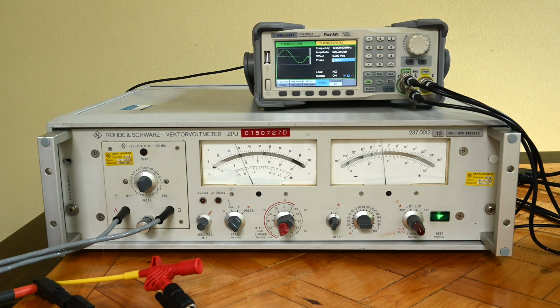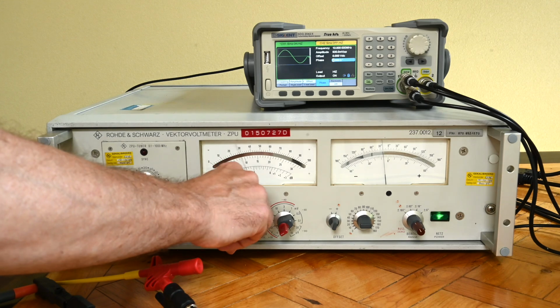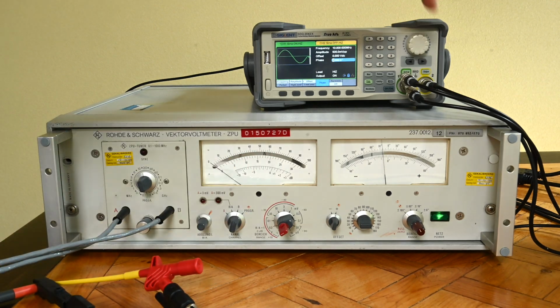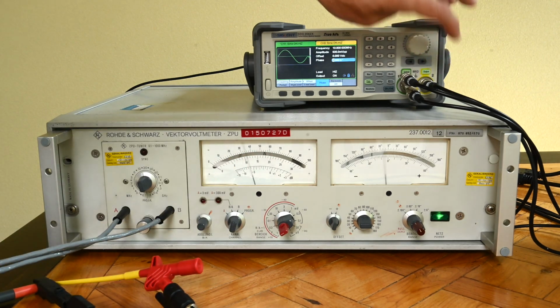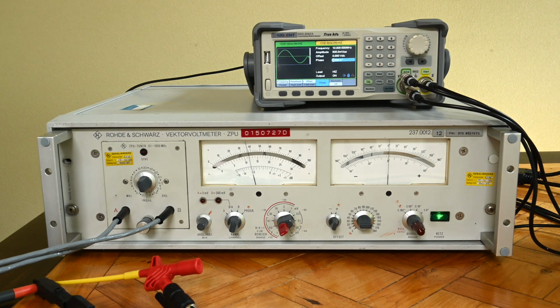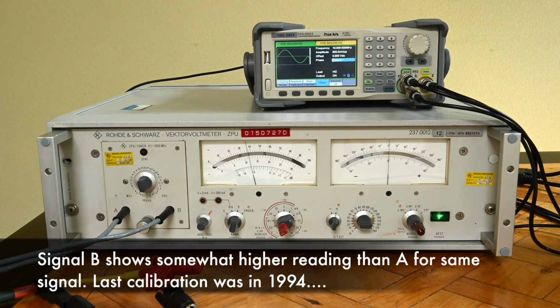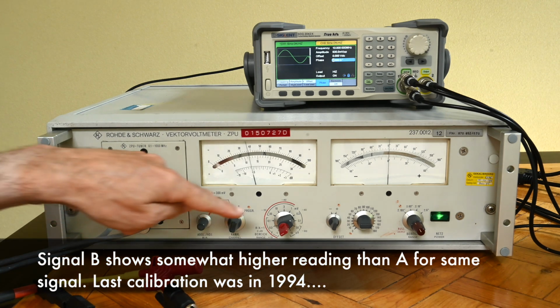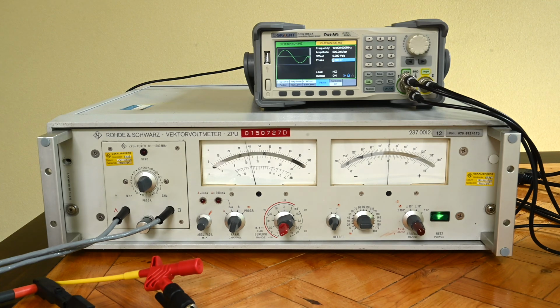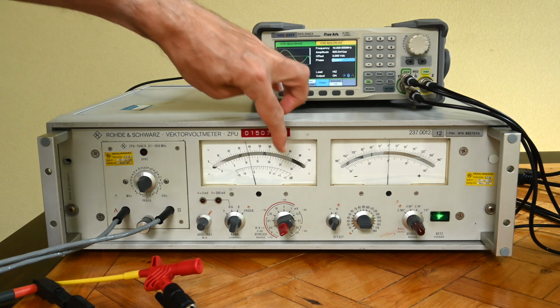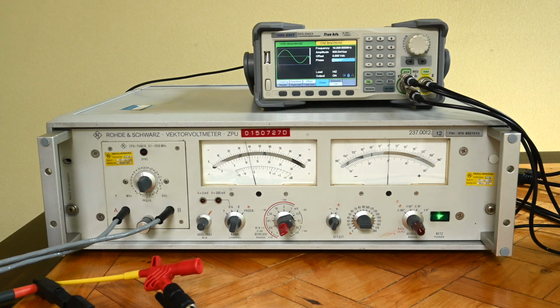Then I want to try the second channel as well, so I'm going to channel B here, and I create exactly the same signal, and I'm turning it on here, and we're getting it on signal B. Now, since this is a voltmeter, we want to measure how much we got here. We are on the range of 0.3 volt full scale, relating here to the 30 that we see over here. So we're reading like 120 millivolts or so.